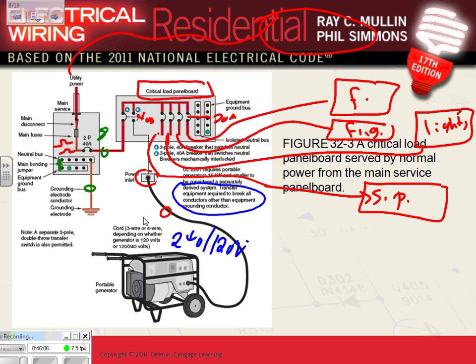A difference between separately derived system, guys, and non-separately derived system: with a separately derived system, you're going to bond the neutral to the ground. But with a non-separately derived system, you do not bond the neutral to the ground. Okay, so this one, portable generator. One of them, okay, separate 3-pole, double throw transfer switch is permitted. And we consider this system separately derived system.